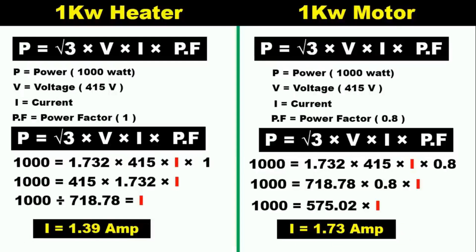So friends, you can see the difference — the current value of the heater is less and the current value of the motor is comparatively high. If asked in an interview which takes more current — a 1 kilowatt heater or a 1 kilowatt motor — the answer is simple: the motor is an inductive load and the power factor of an inductive load is always less than 1, which is why its current value is higher. This applies whether it is 1 kilowatt, 2 kilowatt, or any value — a resistive load always consumes less current and an inductive load always consumes more.